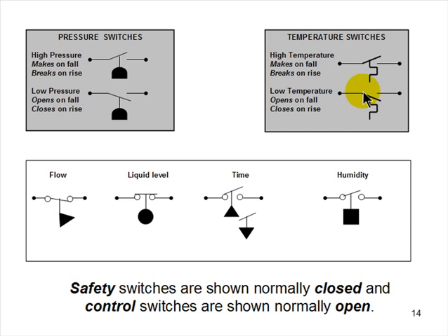When the temperature drops too low, the switch opens and it kills power to the Y leg going outside. So the coil stays cold, the indoor fan keeps running to get rid of that heat, if you will, in the coil, and the outdoor unit shuts off to keep the unit from getting any colder. As it warms back up again, it closes, and the contactor pulls in, and the outdoor unit starts running again, and nobody knows any different. Can't beat a freeze stat if you're zoning.